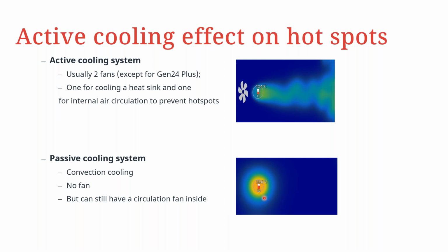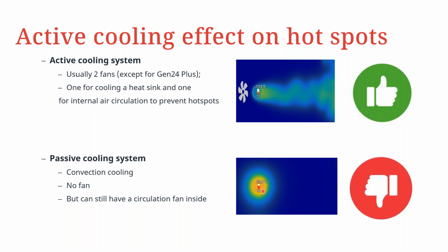Still, you can see that the temperature at one spot is quite high, at 23.6 degrees Celsius. Therefore this can easily lead to creation of hotspots within the inverter. So the first one would be the ideal case, when the temperature is kept as low as possible for the electronics inside. But the next one is not so ideal, because this can easily create some kind of thermal runaway within the inverter if it's not checked.